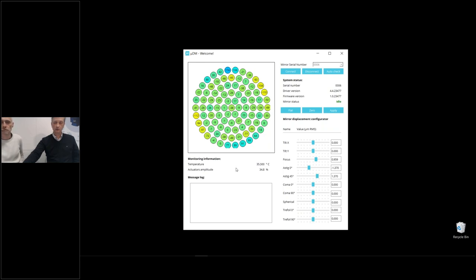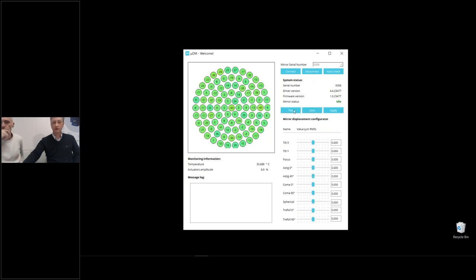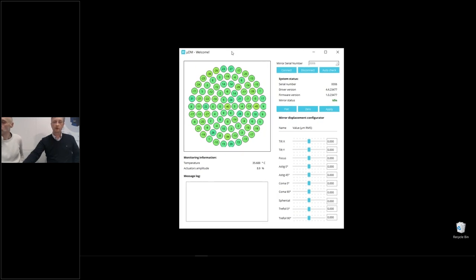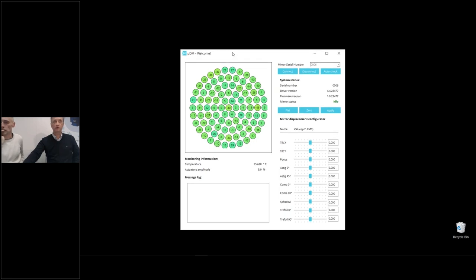The software also shows you the dynamic range used by the mirror — in this case we applied a significant amplitude already, about 34% of the dynamic range — and it shows the intrinsic temperature of all electronics and the membrane temperature. At any point you can apply zero or apply flat. The main advantage of the software is that you can start using the mirror directly out of the box — just immediately after receiving the mirror, you can start using it.